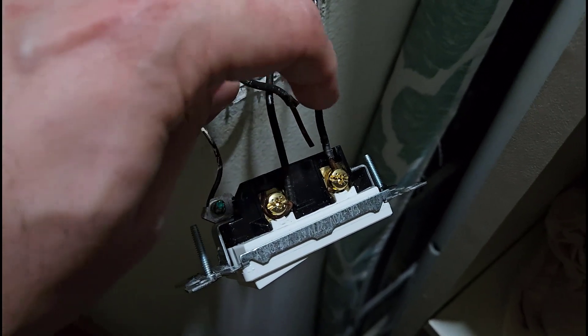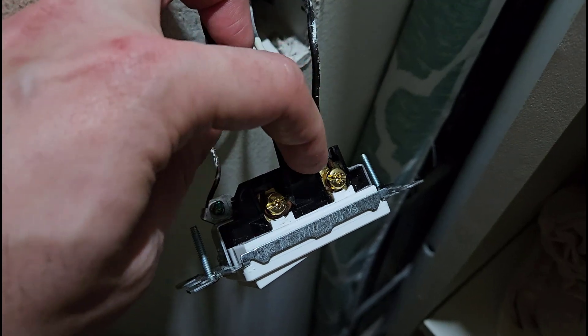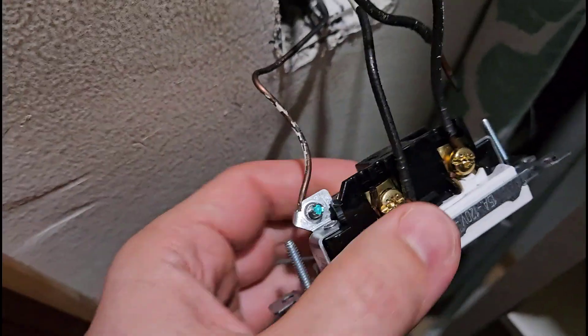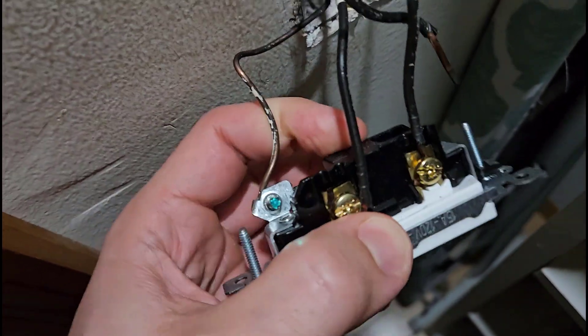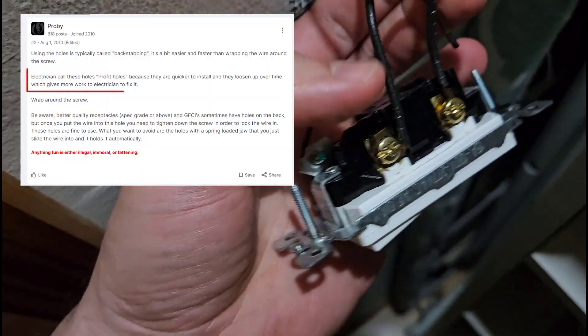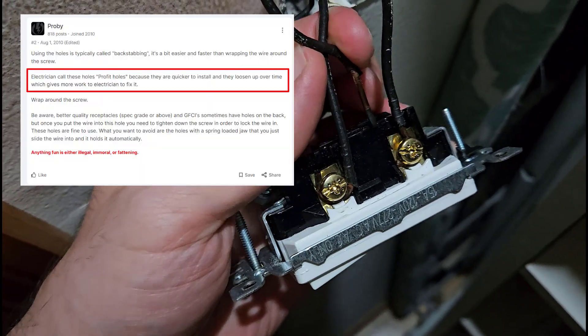It had four wires and two of them were connected using the light switch itself. So one was connected to this screw and one was pushed into the hole on the back of the switch. In general it's considered better practice to use the screws because the wires are more likely to pop out of the holes eventually.